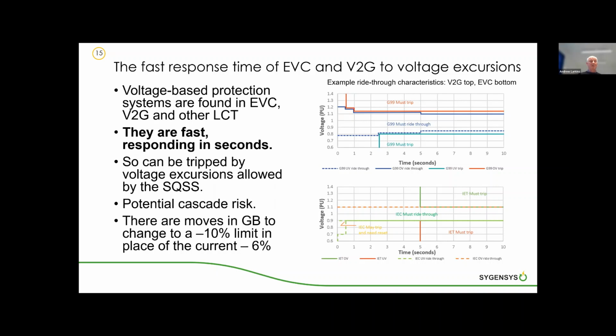And this gives a risk of potential cascade. Specifically, if we consider an overvoltage condition, if there's a small overvoltage condition in one area and we start to lose load in that area, that load is tripping, there is then a risk that voltage goes up further and we have a cascade situation.